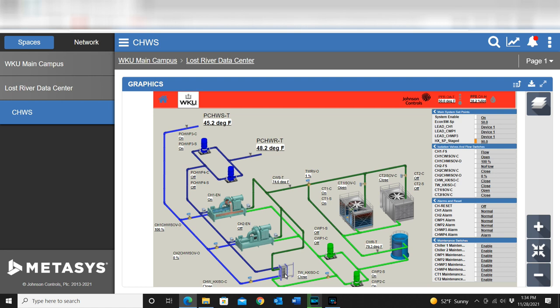In the milder temperatures we don't always get it, but as those temperatures outside fall, we do see a significant drop in the temperature coming through that heat exchanger. Of course, we also have our bypass valve, but typically when we are on plate frame, we're flowing 100% of the water over the towers and virtually none is being bypassed. However, when the chillers run, that story is just the opposite. Depending on the load on the machine, it will modulate the bypass valve, recirculating the water back into the sump, as you can see here, this blue tank.